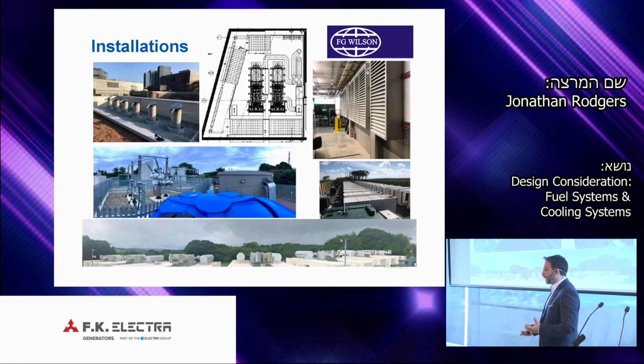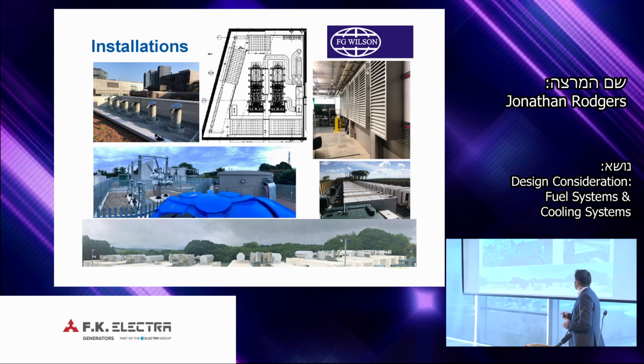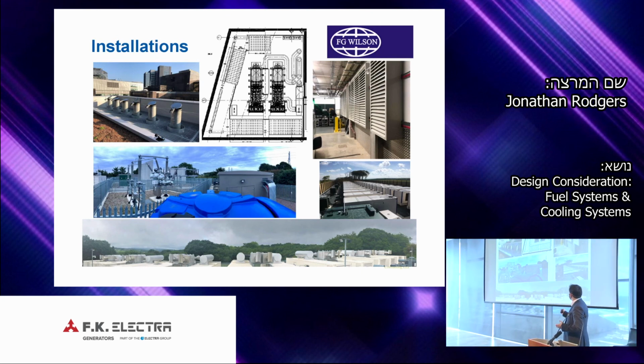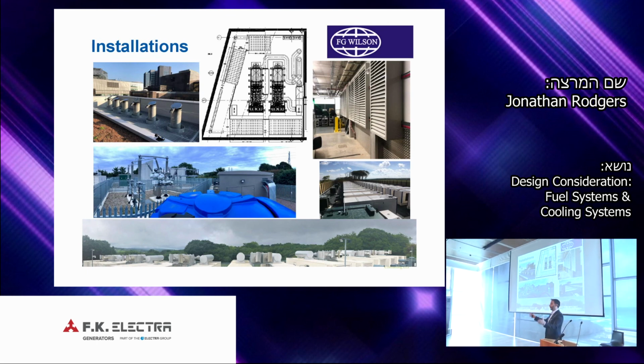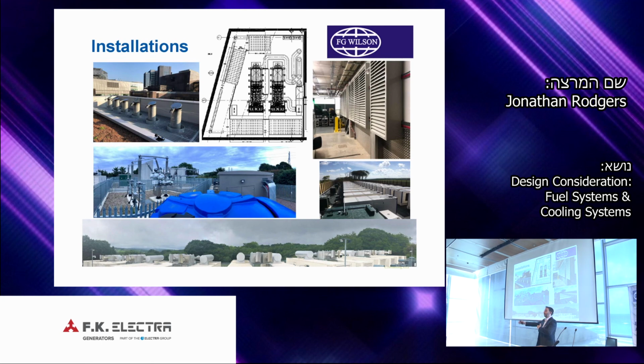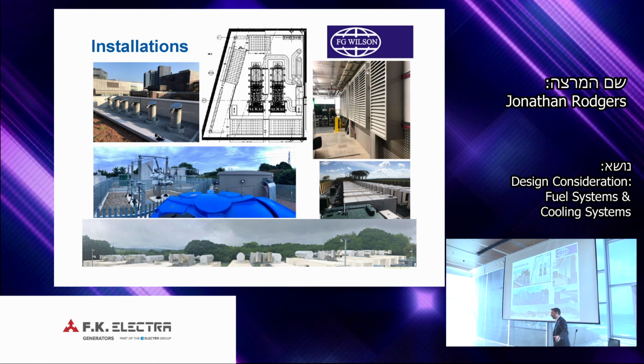So we have many different types of applications. In looking at cooling, we've different arrangements, whether it's standard canopies, where a standard canopy cooling group is selected, but we may have these as an array of multiple generators. So this site has 44 of these. For this cooling, we need to look at how the airflow comes in and how each airflow affects the neighboring generator. So we look at how we can model that airflow performance. It might be containerized. This site has 14, sorry, 1.5 megawatt engines, and we have to look at how the airflow can come into the container, can discharge, and how the hot air from exhaust, how that might interact in the airflow around the system.